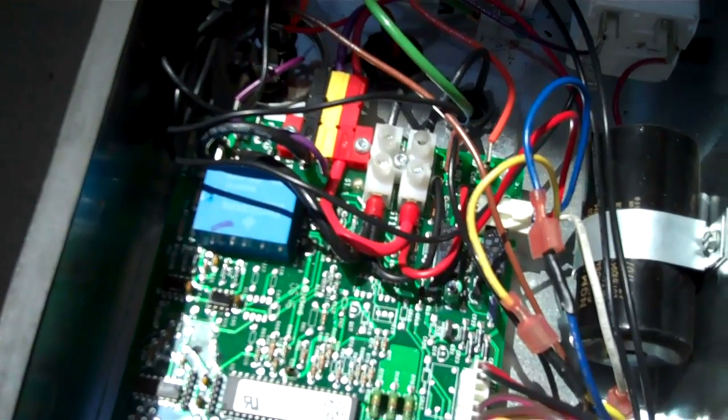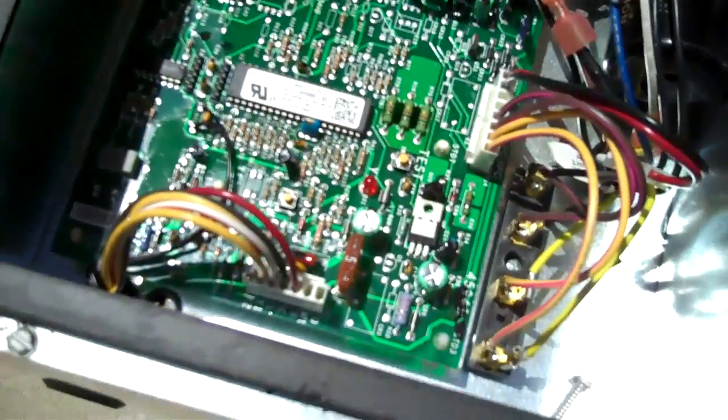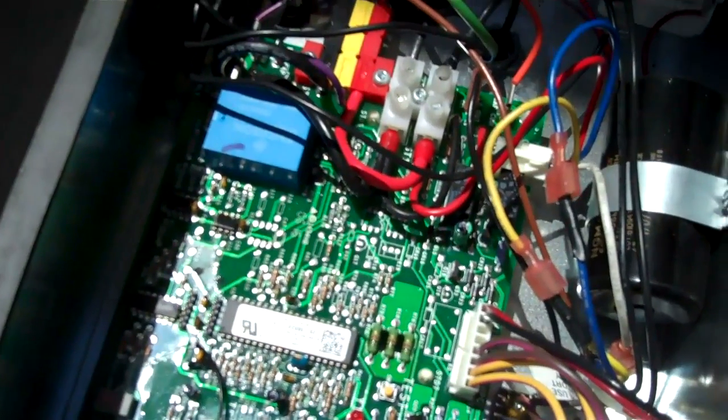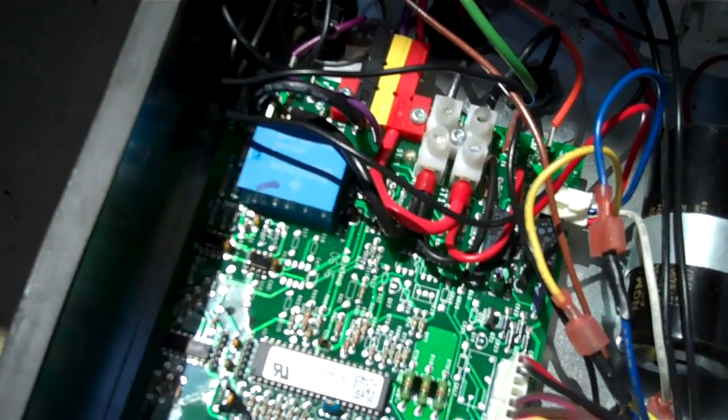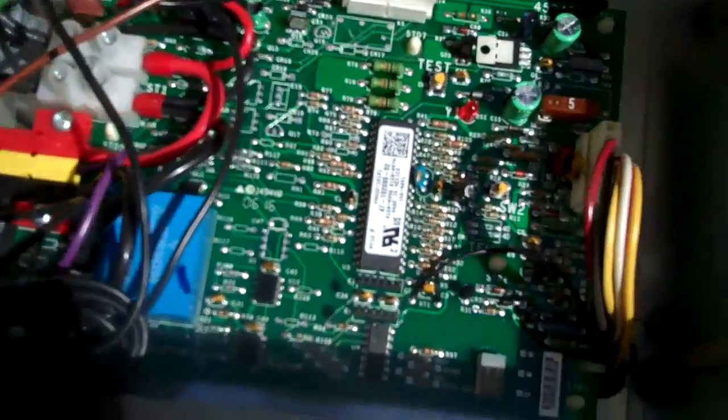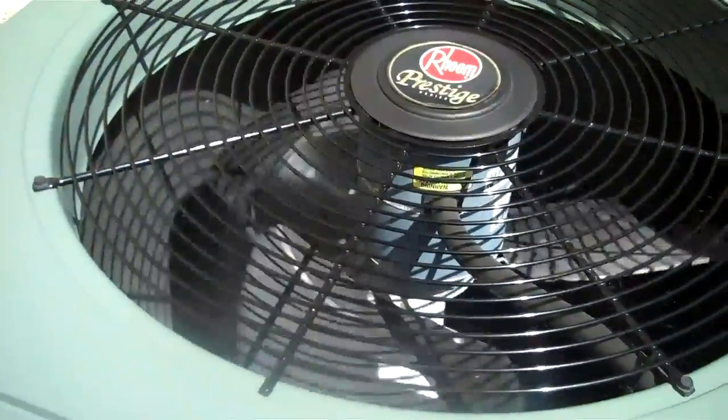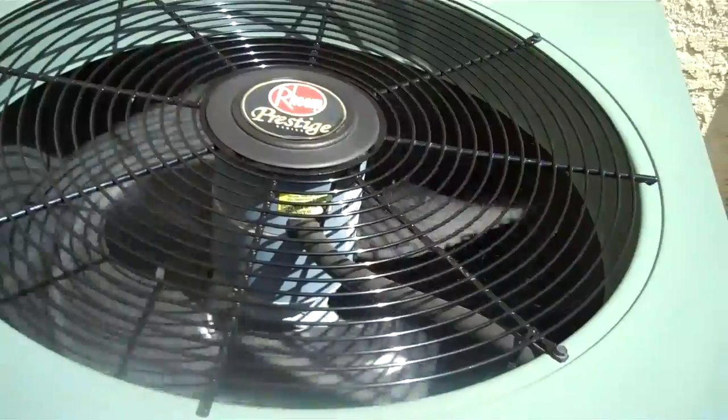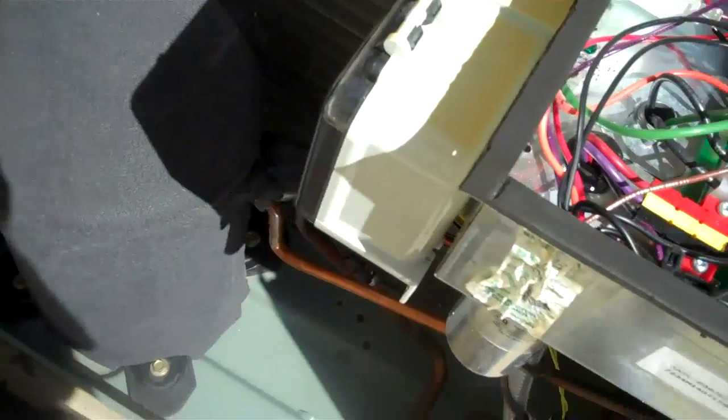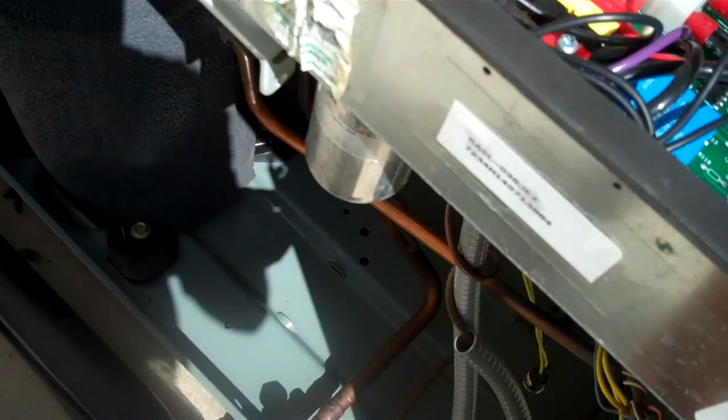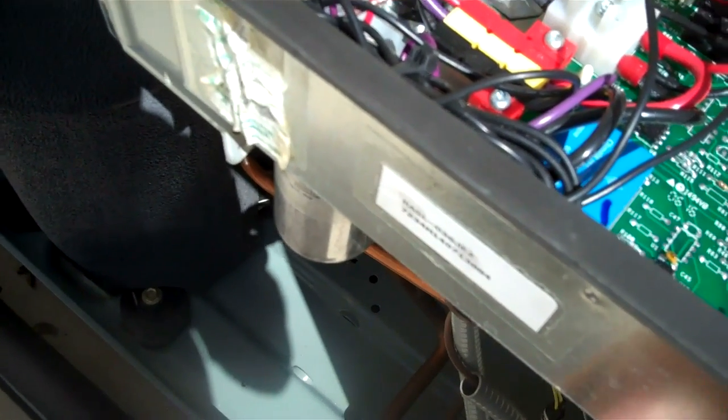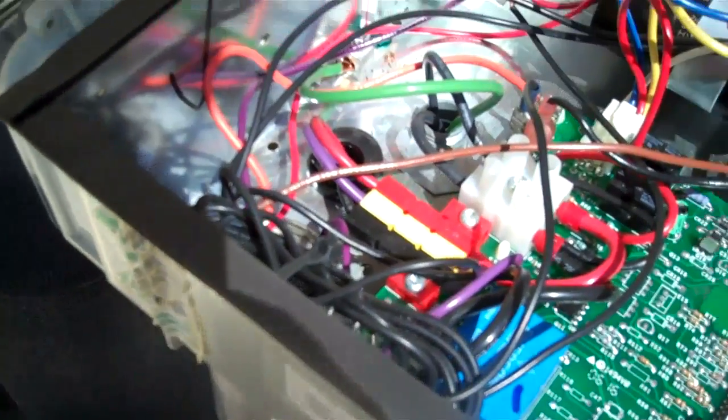I'll show you how you pump it down, it's real easy, but it's kind of funny seeing a unit, you know, up to five tons with that little relay for the compressor. Okay here's the board here with the test button, so I can run through a test pattern. The compressor's going to start first, and then the fan, it delays on the startup and the shutdown because of the inrush current, and then I can actually jumper this down here and give it a call for cool.